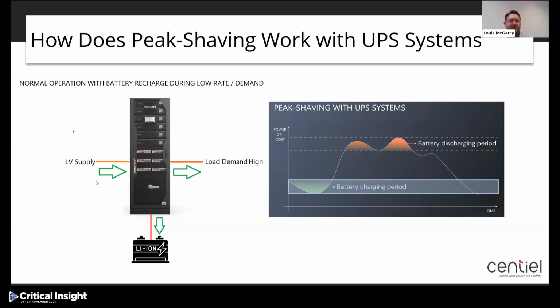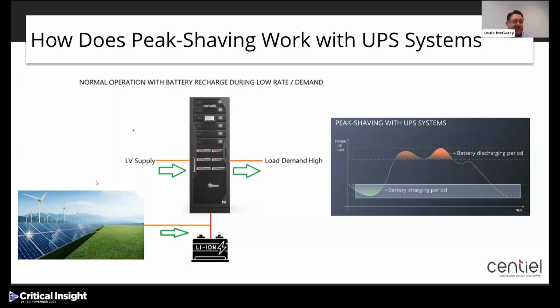Now, once the UPS has reached the end of its peak shaving period, battery recharge can be held off until the low rate of demand or of energy comes into play. Or alternatively, perhaps the recharging could be taken from means such as renewable energies, and therefore the peak shaving operation is potentially completely net zero.